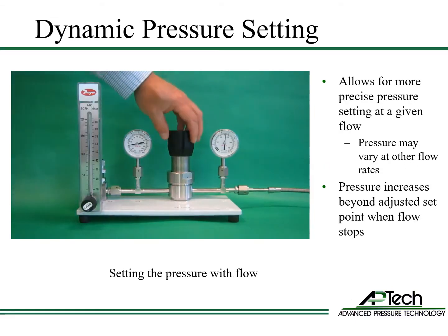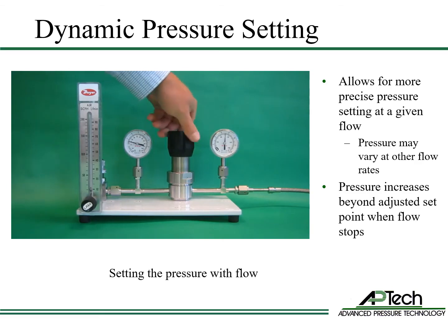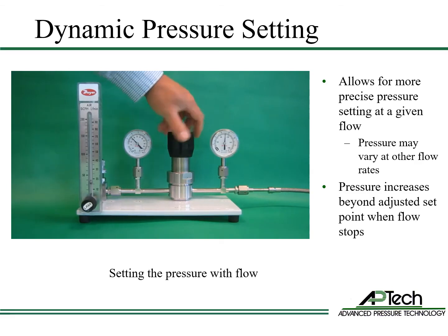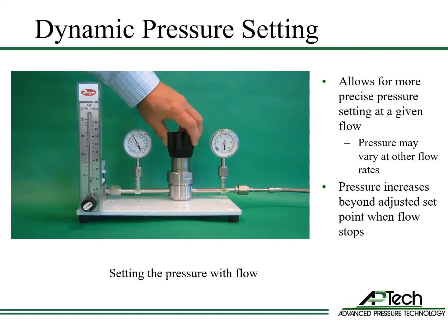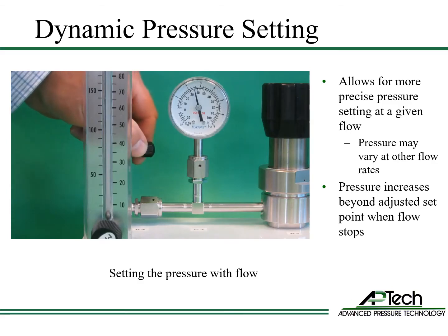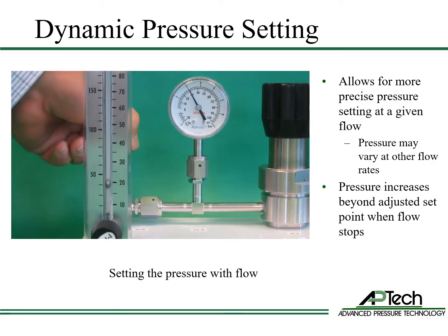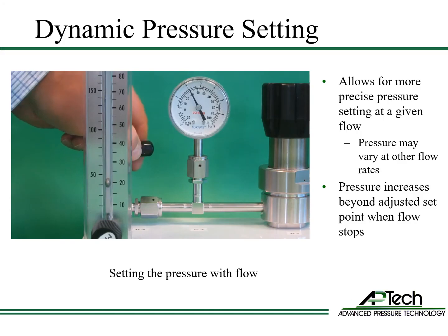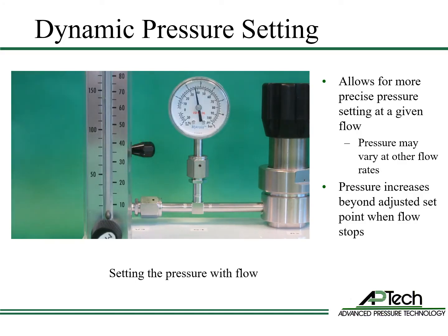Dynamic pressure setting means setting the outlet pressure with flow. This allows for a more precise pressure at a given flow. In this example, the regulator is set with a fixed flow downstream. When flow stops, the outlet pressure rises above the adjusted set point due to droop. If the flow rate changes later, the outlet pressure will vary.